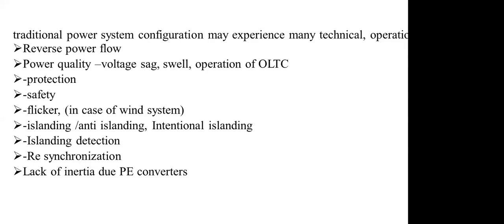Resynchronization is one of the major issues in renewable source integration, because once a grid fails and comes back, we need to match the phase angle and voltage level. If you don't match these two when reconnecting your DG system into the grid, you will see a lot of fluctuation at the PCC, the point of common coupling, with a lot of voltage and current fluctuations. That is not very acceptable from the grid's point of view, so you have to do proper resynchronization once the grid is restored. That is one of the problems you see with renewable sources.